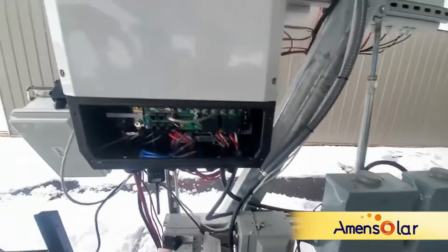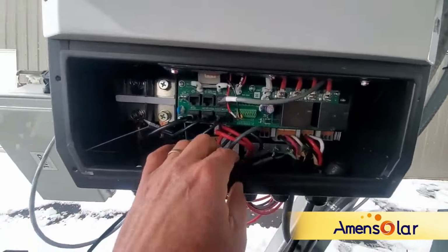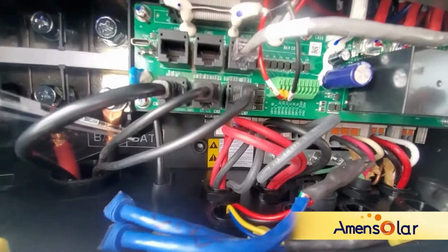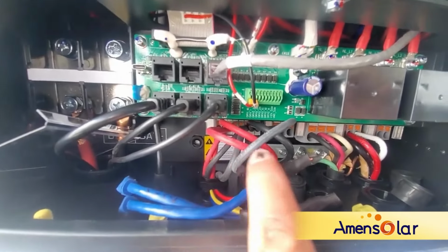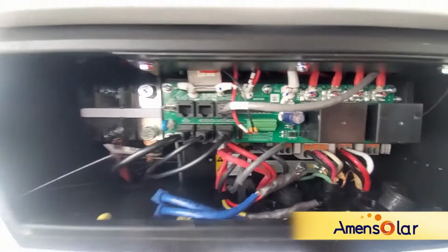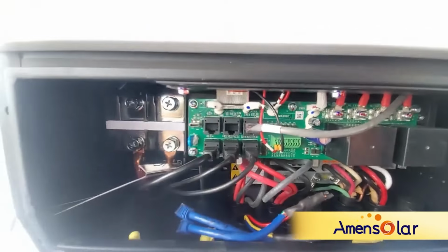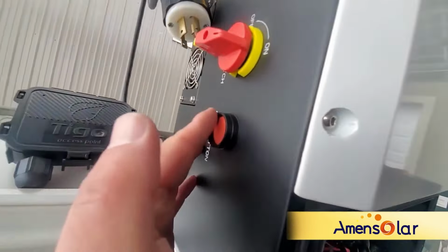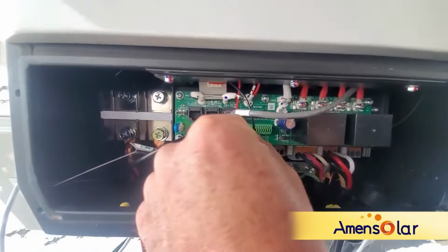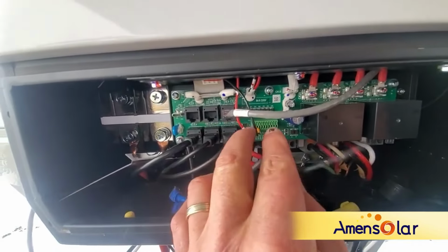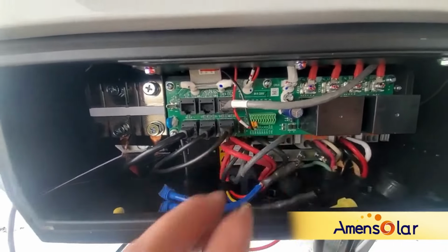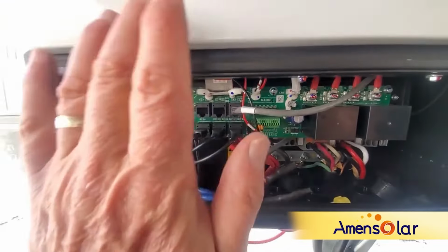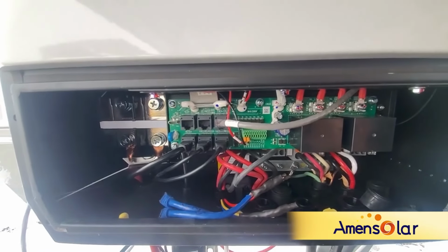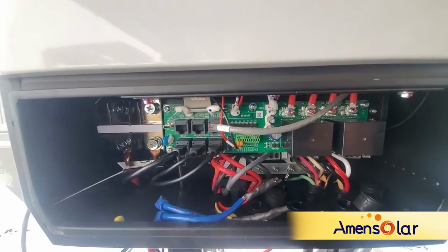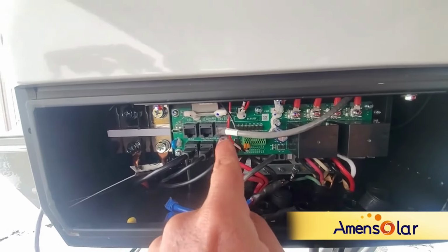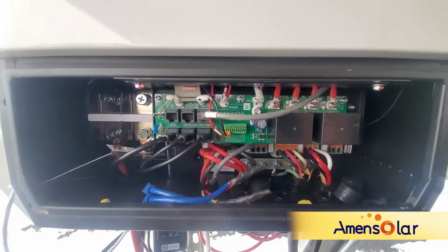So right now it's set up as lead acid batteries, and so we have got 4 solar inputs, 4 red, 4 black, individual. This is the switch, the wires for the switch that wire into there. If you need a rapid shutdown, all you do is put the rapid shutdown in series with these 2 wires. You pull this wire out over here and you put your rapid shutdown or your emergency stop switch outdoors in series with these wires. At the moment this circuit is broken, the inverter will shut off.